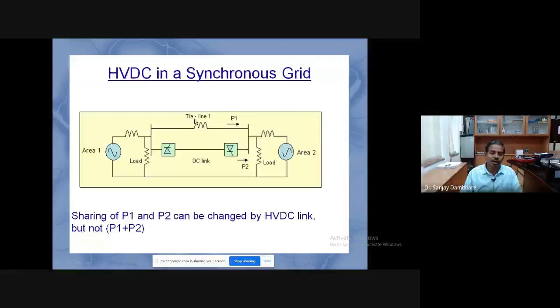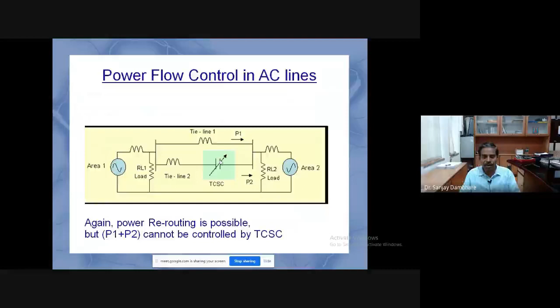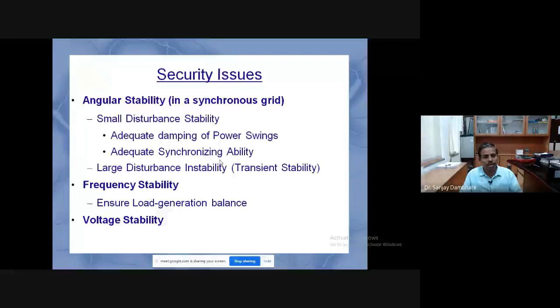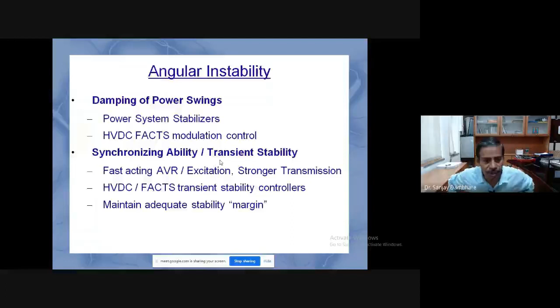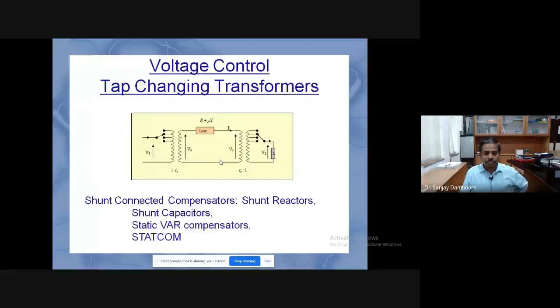The reason I am telling this point is that all these FACTS controllers are putting some pressure on the power system protection engineer, and that is how it is to be looked into. So while going to the protection, we must understand what is happening in the power system. Anyway, I will skip this slide. You had a session on stability. We have angular stability, frequency stability, voltage stability, and the devices which can improve the stability of the power system: the power system stabilizer, the HVDC and FACTS controllers, and likewise.